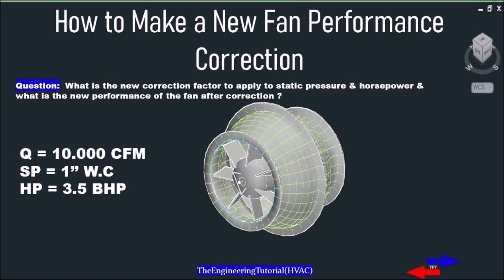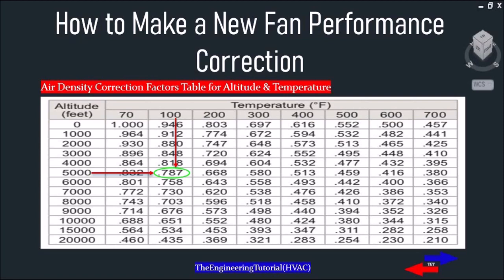But after installation, the fan is operating above standard conditions at an altitude of 5,000 feet above sea level and a temperature of 100 degrees Fahrenheit. So what is the new correction factor to apply to the static pressure and horsepower, and what is the new performance of the fan after correction? As you can see, this is an air density correction factors table for altitude and temperature.